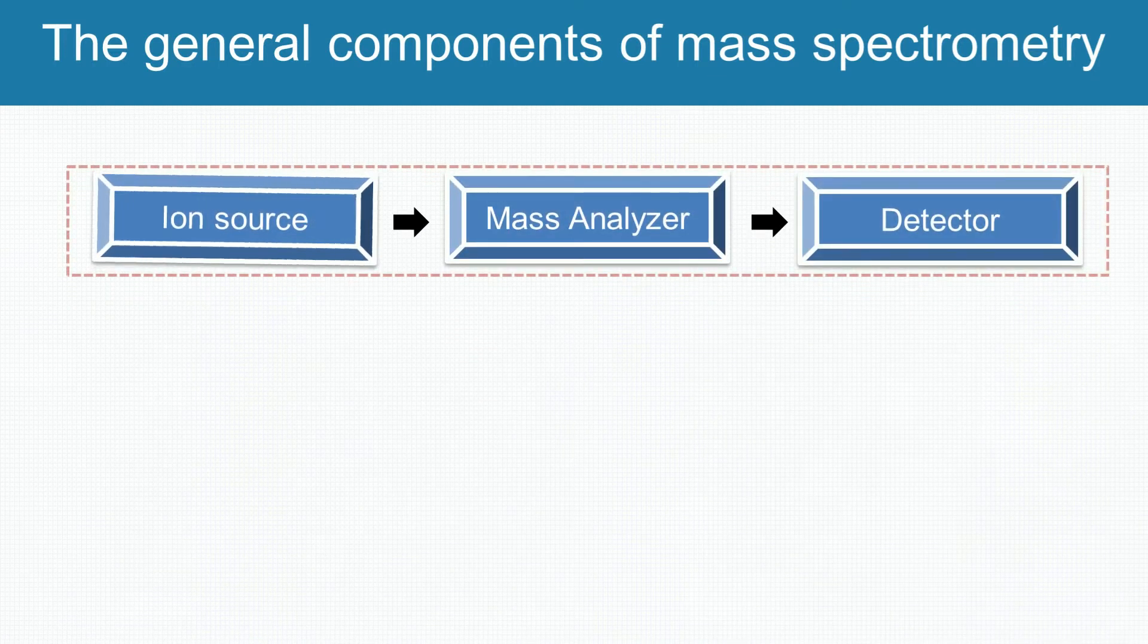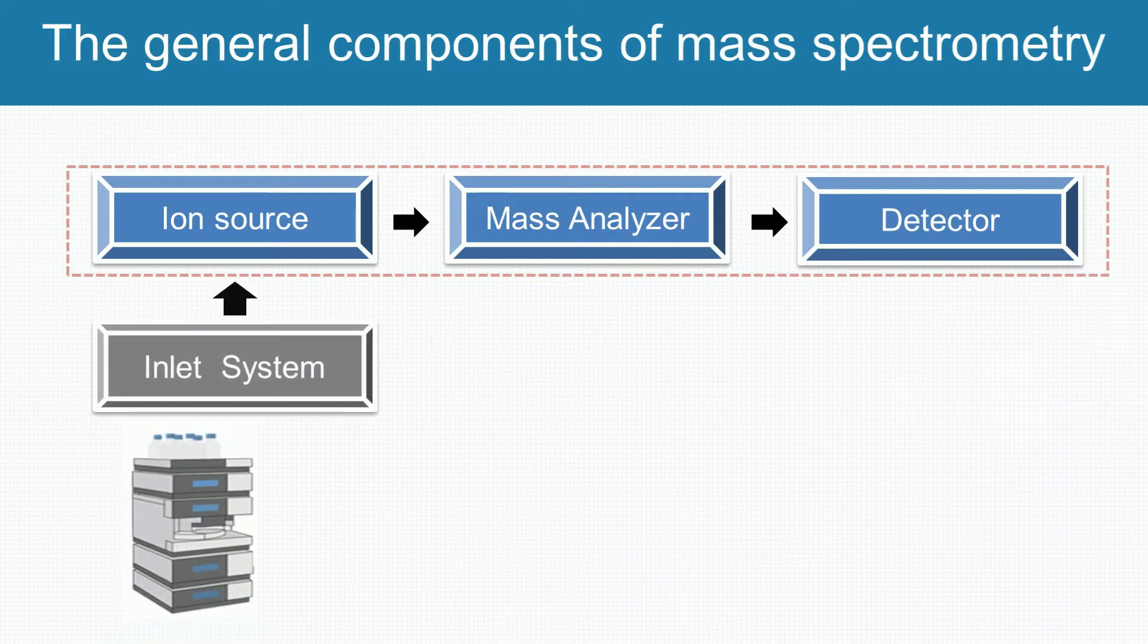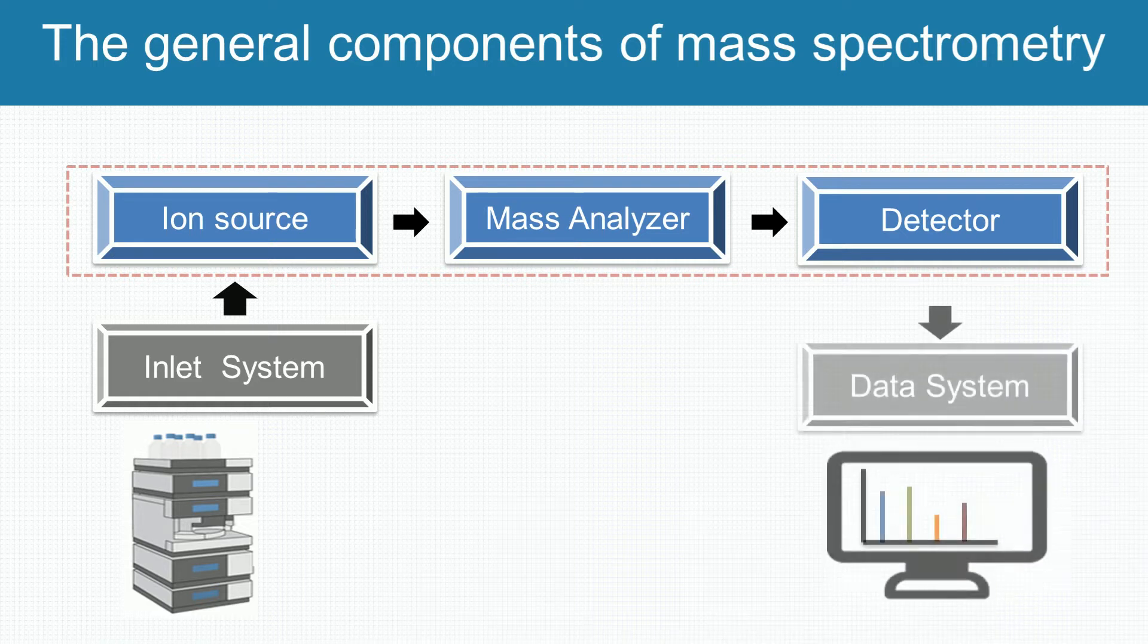The mass spectrometry consists of three main components: the ion source, the mass analyzer, and the detector. In the mass analyzer, the ions are sorted and separated according to their mass and charge. The sample introduction system is essential to introduce the samples into the ion source. A computer and software are also important.